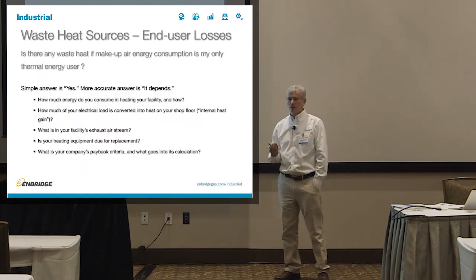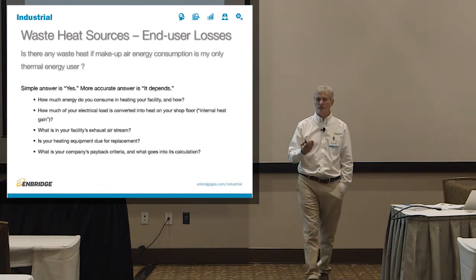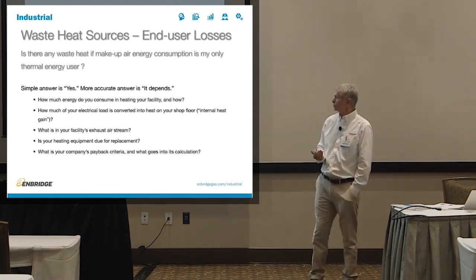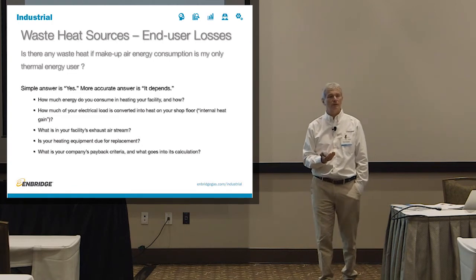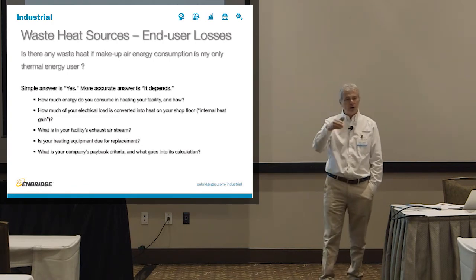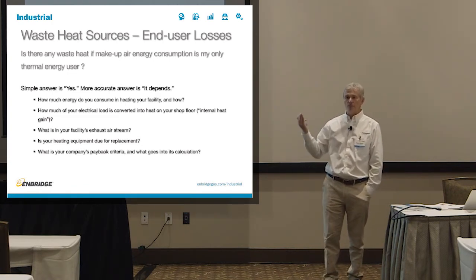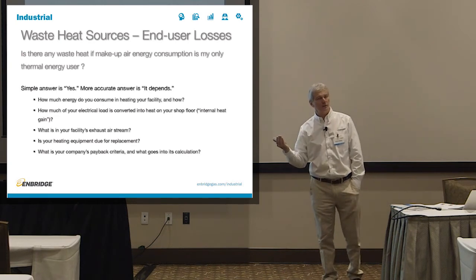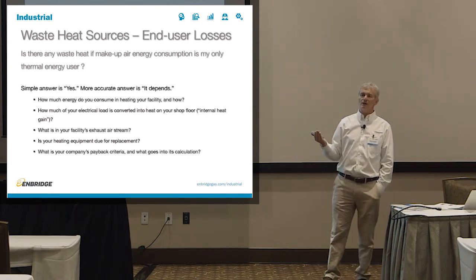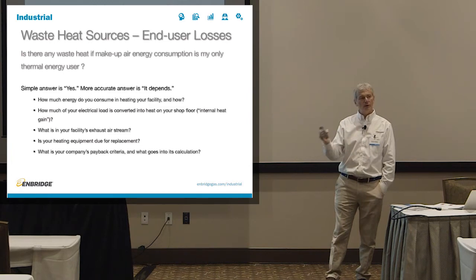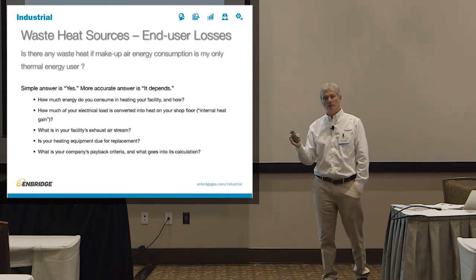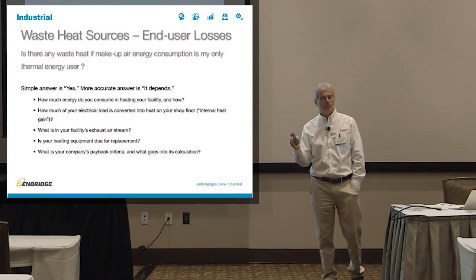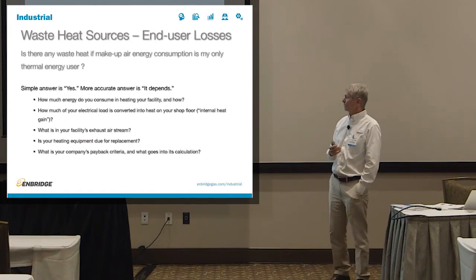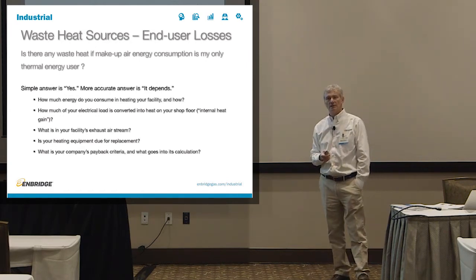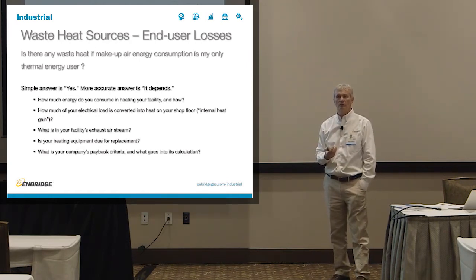So the things that we have to always question are the same. How much energy do you consume in heating? We've seen the profile, but is that profile telling you you're using a total of 50,000 cubic meters a year or 2.5 million cubic meters a year? Either one is a valuable thing to know. How much of the electrical load is converted into waste heat? How much waste heat do you have?